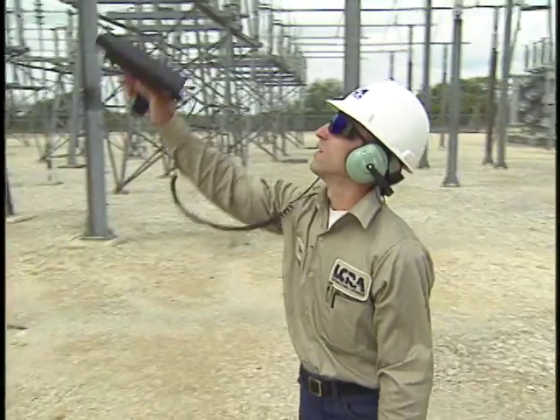So we don't just base our judgment off of one test. When we see a flag go up, we start saying, okay, let's do this on it. The next progression is to do a DGA on it, and then we get those results back. After we get all of the results in, we make our assessment on that piece of equipment, and we determine whether we need to perform maintenance on it, pull it out of service for emergency repairs, or whether it's just a normal characteristic of that piece of equipment.